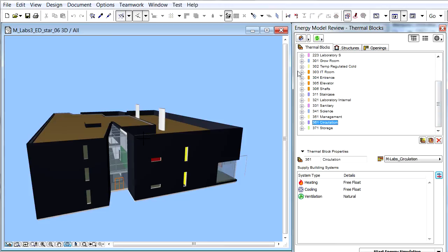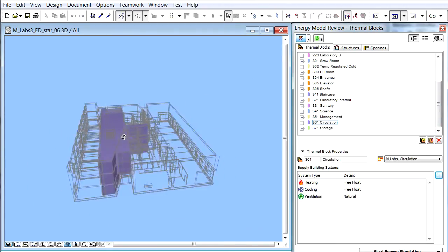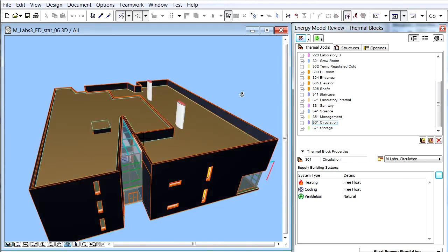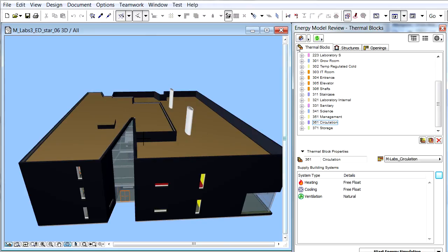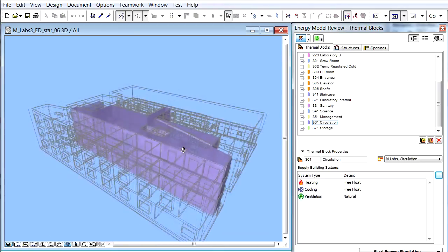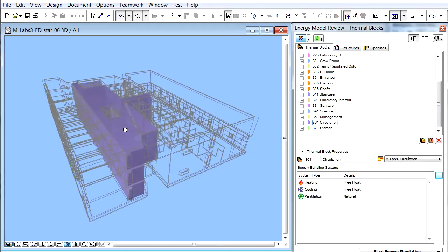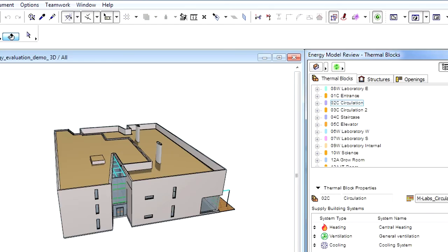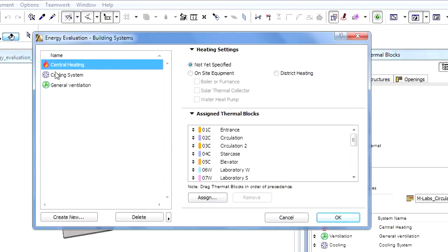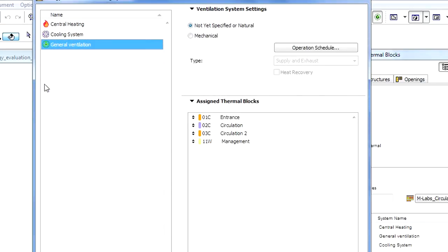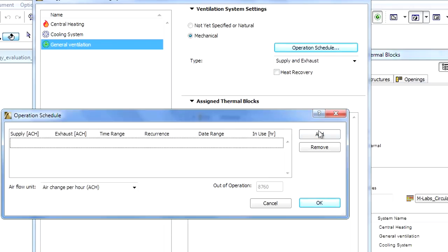Finally, let's see a unique example. The circulation thermal block is located in the middle of the building and has staircases and corridors. It also has a curtain wall facade at the entrance and a glazed top above the entrance. Typically, this circulation area would have a thermostat controlled heating and cooling system. In this example, we will utilize this atrium area as a buffer zone with controlled natural ventilation. Night-time ventilation is typical for climates where the air is cool at night and can be used to cool the building down. During wintertime, solar gain can be provided with the help of the glazed atrium. To achieve this, we will select Not-Yet-Specified or Natural for both heating and cooling systems, define a supply and exhaust ventilation system, but set the air flow to zero.